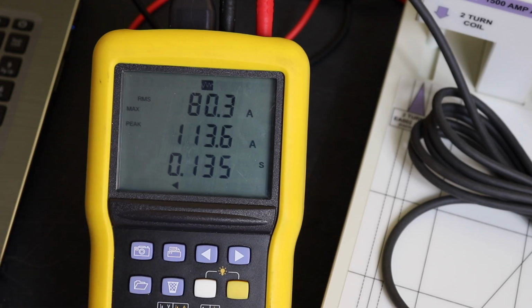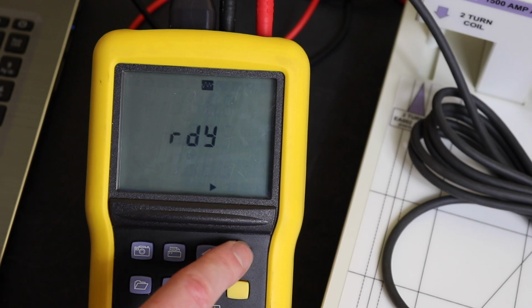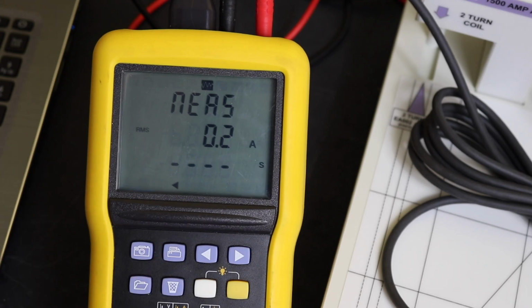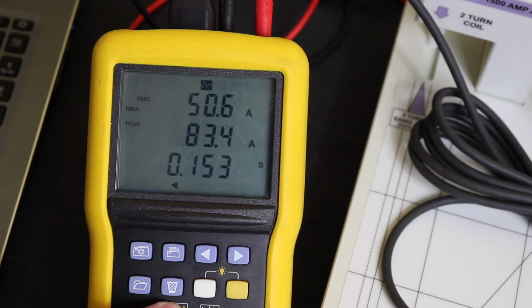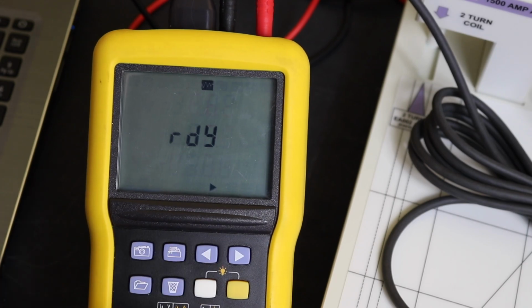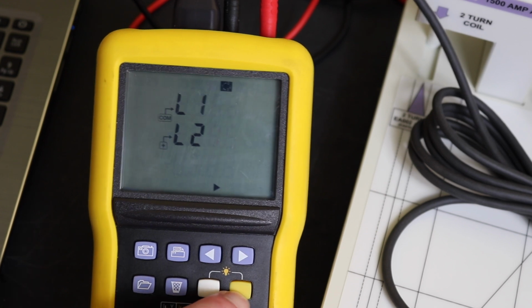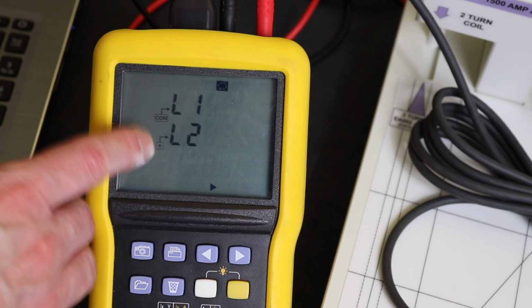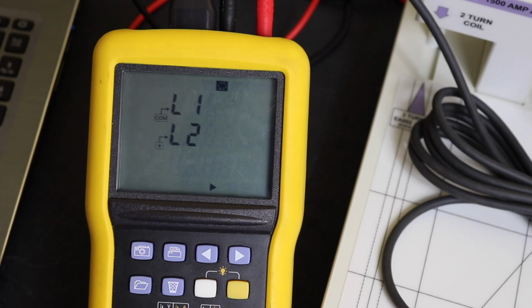If you want to repeat the measurement, you just hit the 2 arrows and we can go again. So 50 amps I'd set it to, and it's come out to 50.6. Again, the peak will be 1.4 times, I guess. So yeah, that all seems quite good. The second function off of this switch is phase rotation, which you get to on the yellow. So you just measure the L1 and then the L2, and it should give you the phase rotation. Obviously I can't demo that, it's only a single phase injection test set, so that will not work.